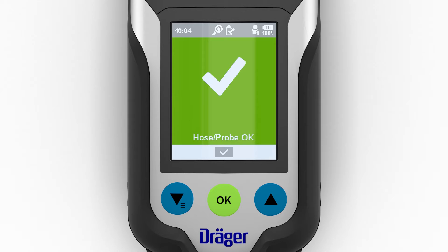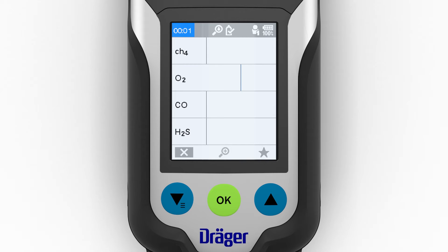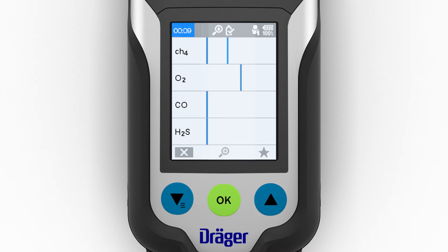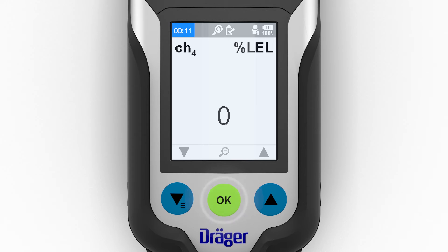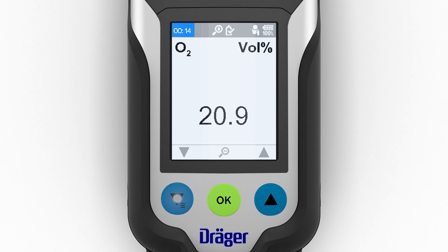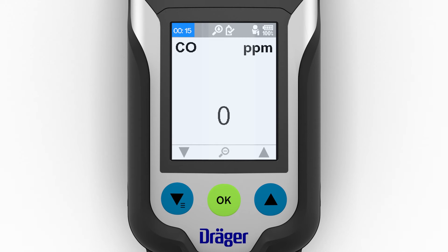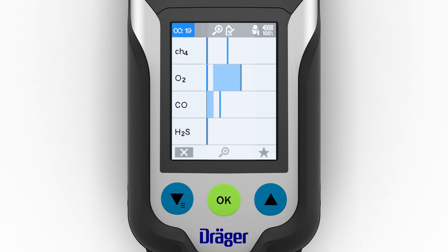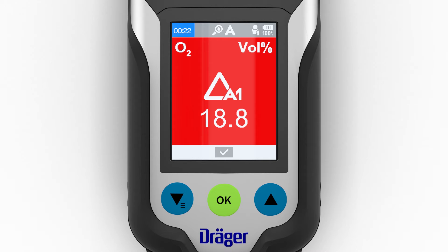Once the pump test is completed successfully, a window will appear in which the gases can be displayed in the form of a bar chart, improving the overview. The diagrams show the current values and the peak values. In single gas view, an audible signal sounds at the same time, and the frequency of this signal increases as the gas concentration rises. If a gas reaches the pre-alarm threshold, the gas alarm is displayed.